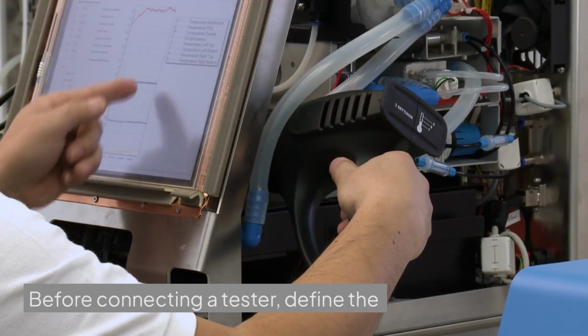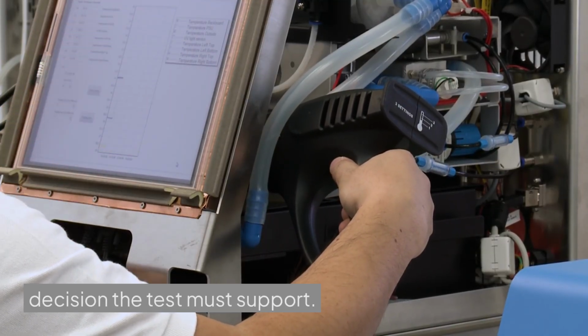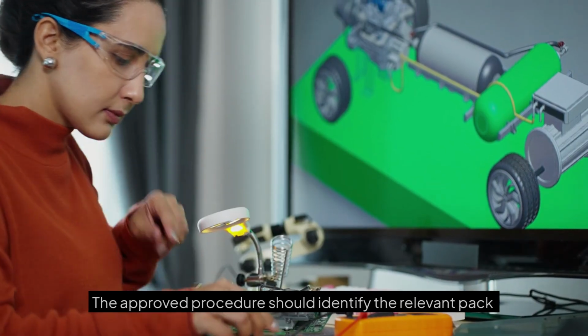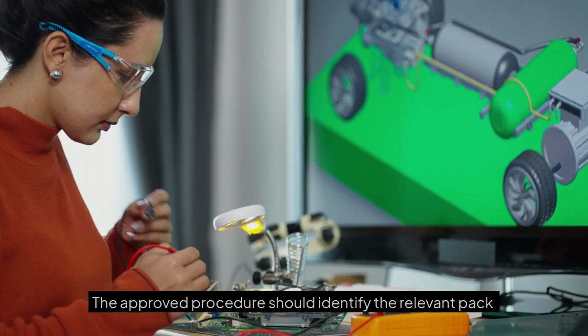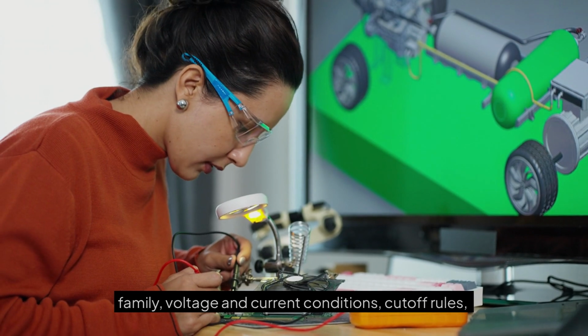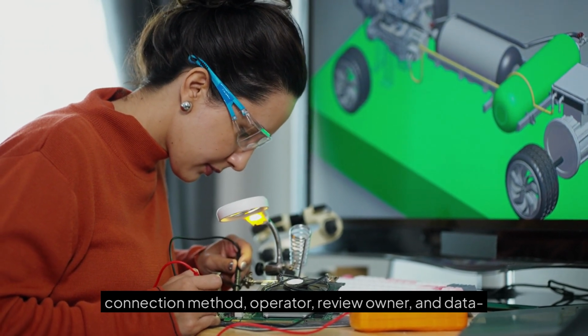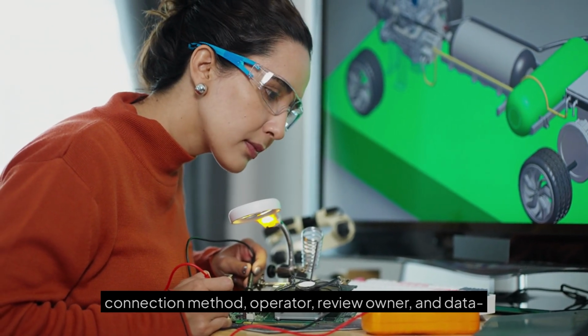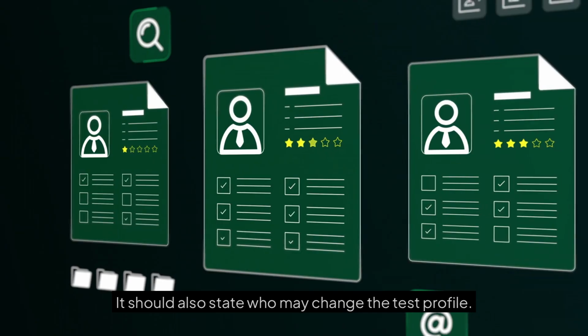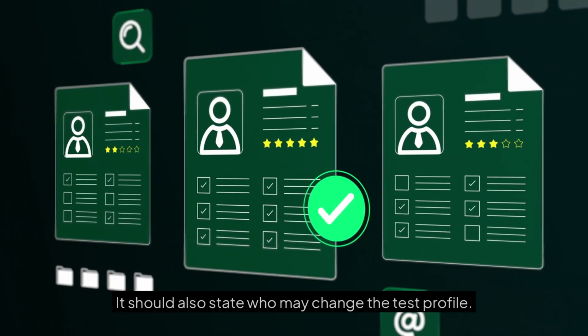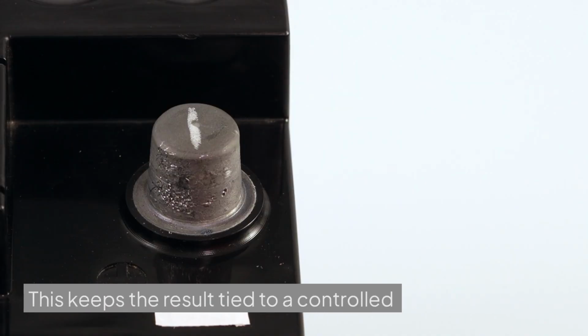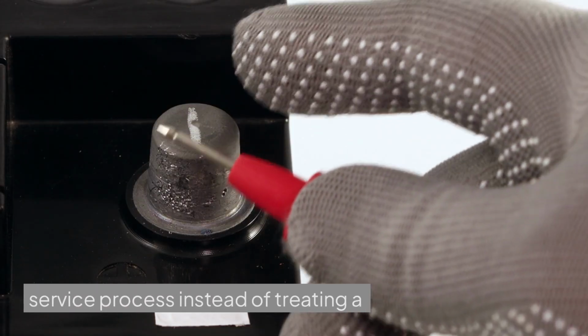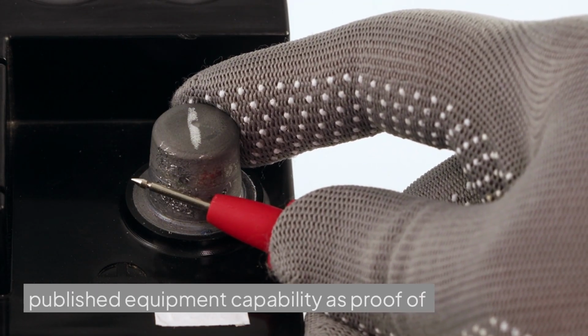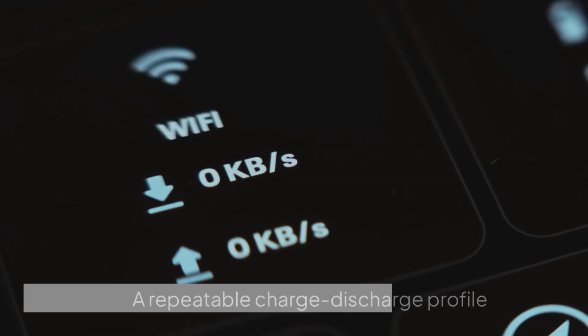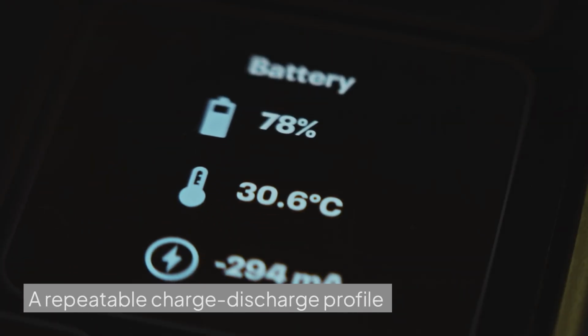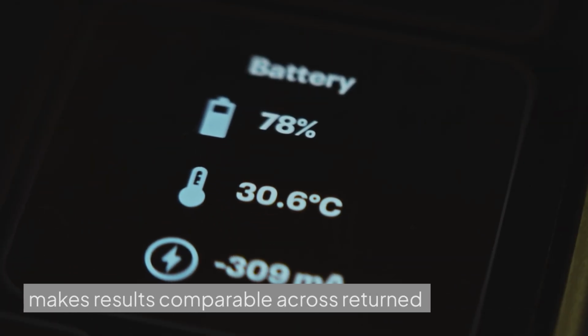Before connecting a tester, define the decision the test must support. The approved procedure should identify the relevant pack family, voltage and current conditions, cutoff rules, connection method, operator, review owner, and data retention requirements. It should also state who may change the test profile. This keeps the result tied to a controlled service process instead of treating a published equipment capability as proof of suitability.